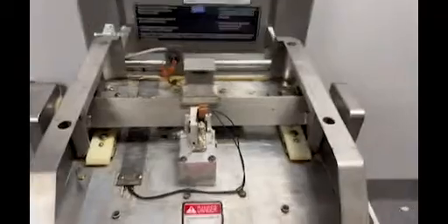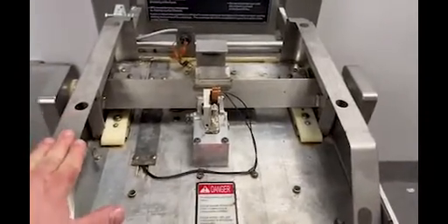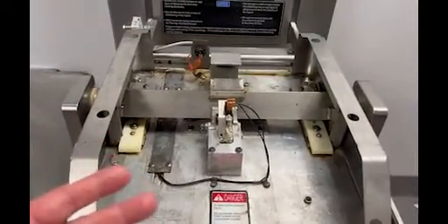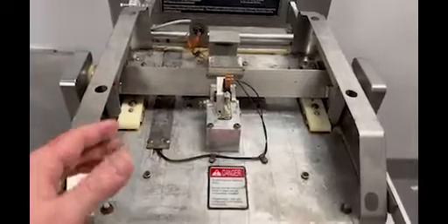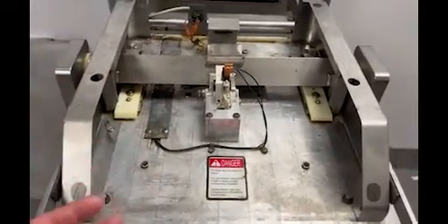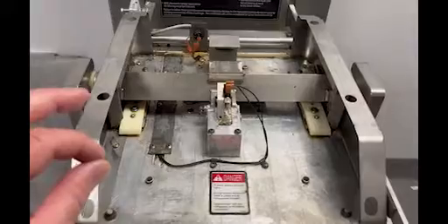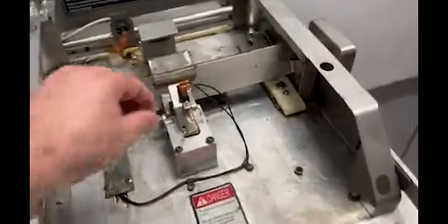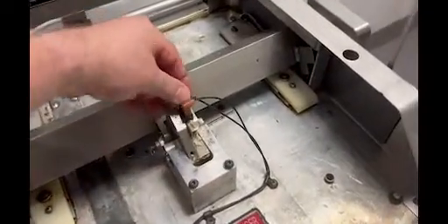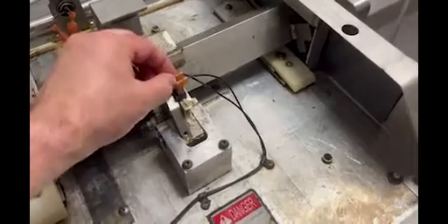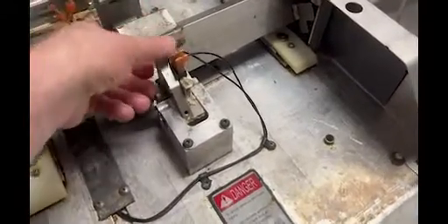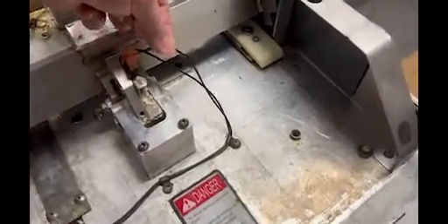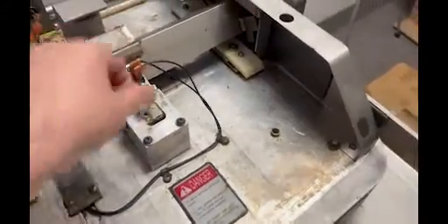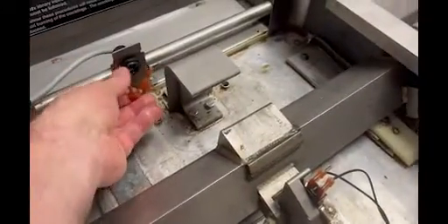Now as I begin to troubleshoot, with my cover off, assuming I don't have a voltmeter and all I have is a Phillips screwdriver, the very first and most obvious thing I'm going to look for, especially with an E84D error code, is to make sure all my connections are good. I have opened up lids and found these disconnected, so we want to make sure these are connected and none of the wires have come out. You can even check this one over here.